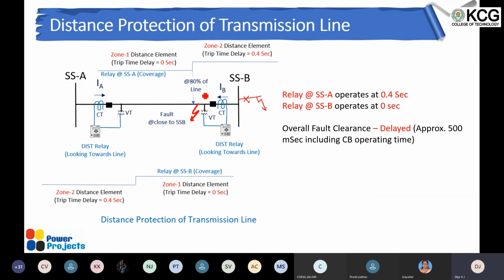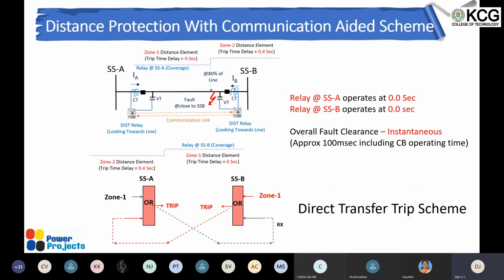With communication, we can do faster tripping even for a fault at 80% or after 80%. So here, we'll take the case of the same fault. Zone 2 is operated at one end, and zone 1 is operated for the substation B fault. See here, zone 1 reaches up to this point for the relay at substation B, so this fault will be seen as zone 1. Once zone 1 is operated, it directly gives a trip command to the respective breaker. Okay, this breaker is tripped. At the same time, it sends a digital signal over the communication network to the other end relay.